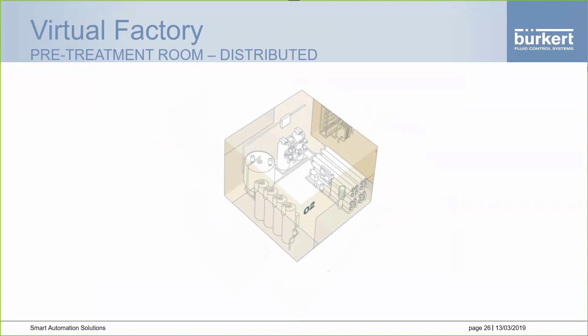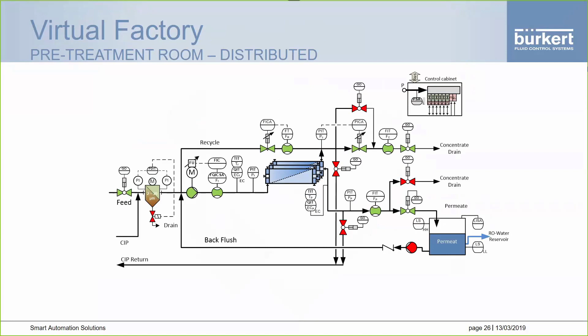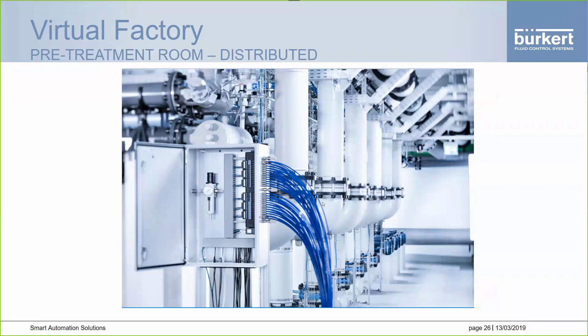Many valves could be used in each of these areas, performing different functions like, for example, backwashing and cleaning of different filters or membrane integrity testing, for example. As each area is spaced apart and some of the valve actuators are quite large, it was well suited to look at a distributed automation system. This would allow us to keep each automation cabinet closer to the valves being actuated in each location, meaning smaller pneumatic tube runs, allowing higher airflows for those bigger actuators.